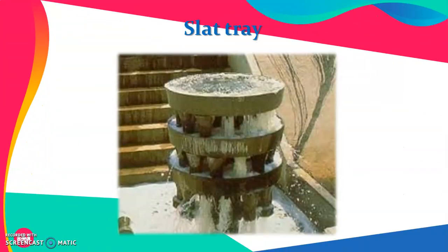Next is slat tray aerator. This is the most commonly used again. It consists of a closed round or square structure consisting of a series of closely stacked superimposed slat trays. Water enters the top of the aerator and is evenly distributed over the topmost tray first.